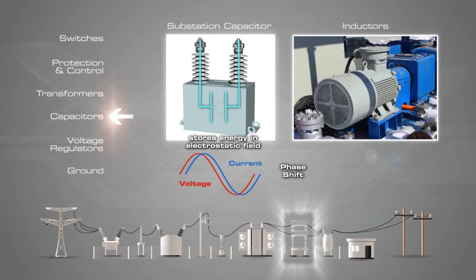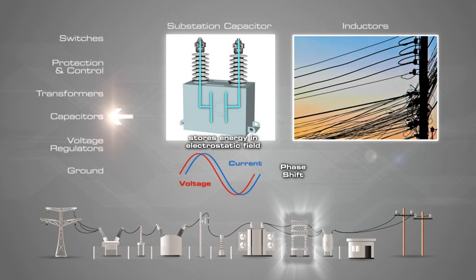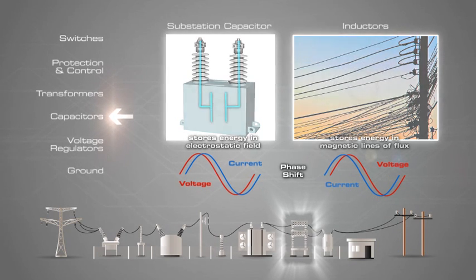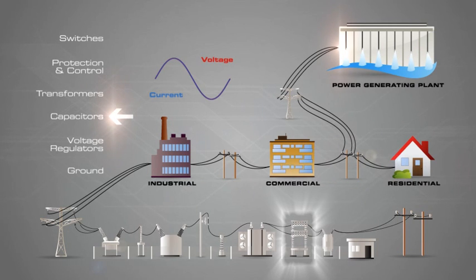Capacitive loads will cause a phase shift between the voltage and current where current will lead voltage. Inductive loads such as motors, transformers, inductors, and wire also cause a phase shift between voltage and current. Inductive loads store energy in the form of magnetic lines of flux, and the phase shift caused by an inductive load is opposite to that of a capacitive load, where voltage will lead current. Capacitor banks are used to correct the phase shift caused by the inductive nature of the transmission system and the loads.